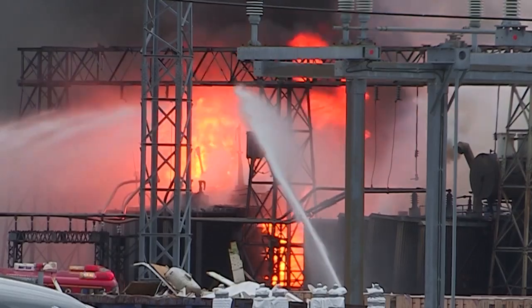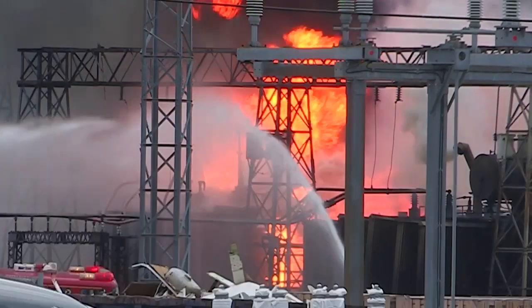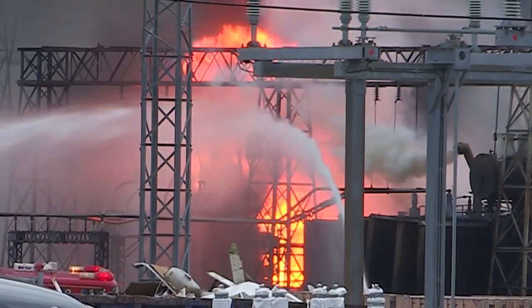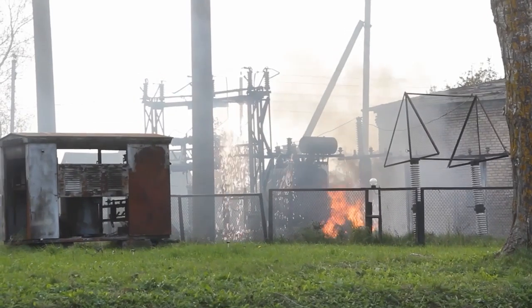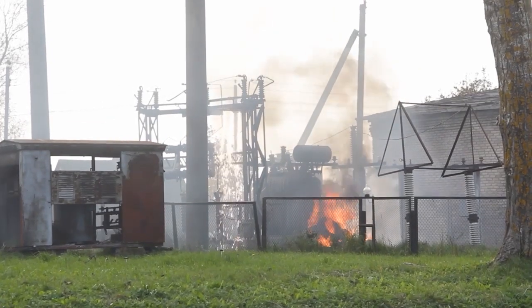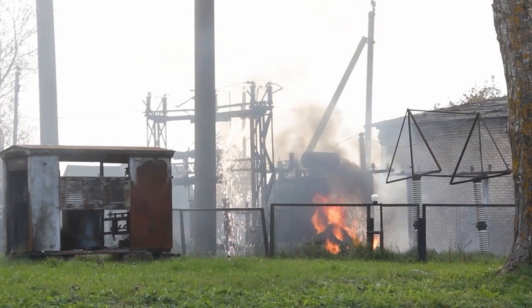Mineral oil is much less friendly to the environment. It doesn't biodegrade the way natural esters do, and it's got a low fire point. And I think most of us have seen videos, unfortunately, of transformers that have caught on fire when something has gone wrong inside the transformer. One of the bad things about mineral oil is once it starts to burn, it's very difficult to put out. It feeds itself, and typically fire departments just kind of stand back and try to contain it so it doesn't go anywhere, but they just let it burn itself out.